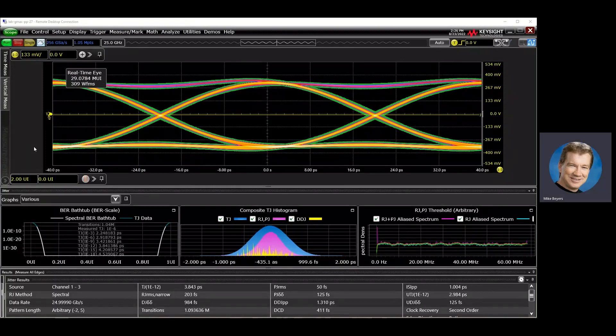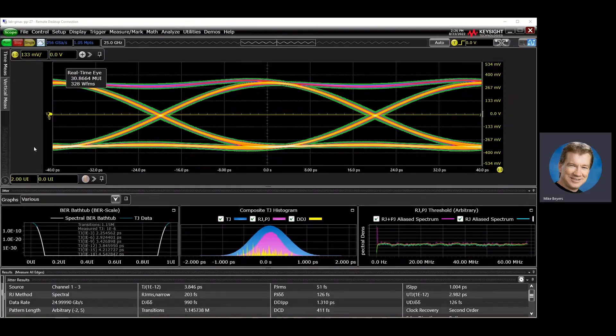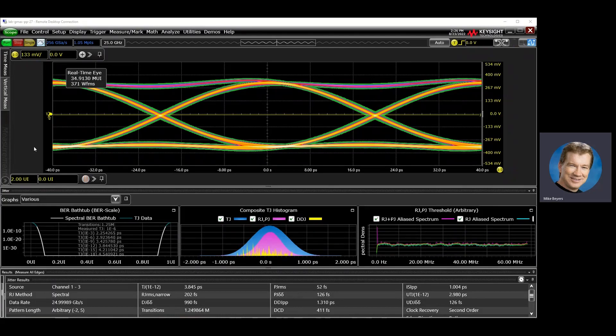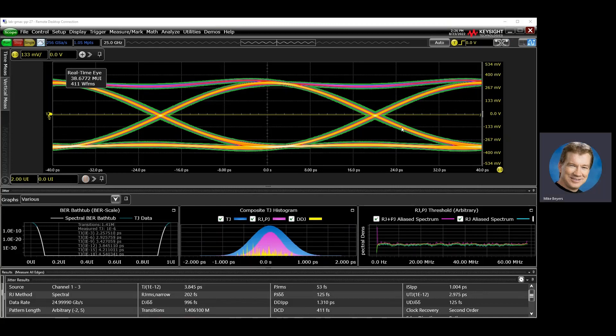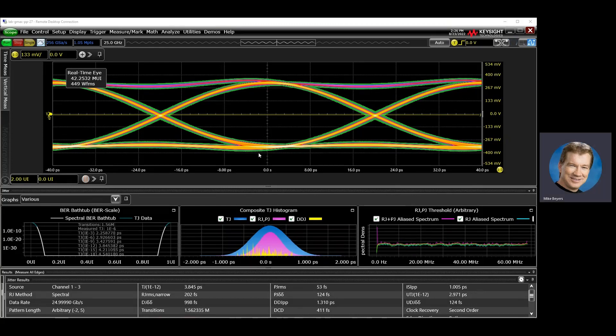Let's look at another new feature in the Infiniium 11.4 software release: eye contours for NRZ waveforms. Up top here, I have a real-time eye of a nice clean 25 gigabit per second symbol.